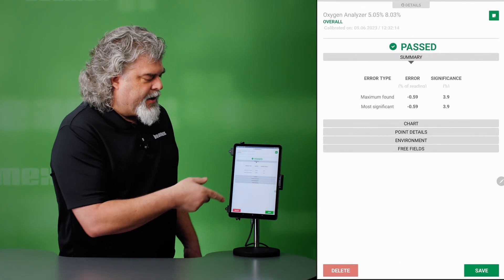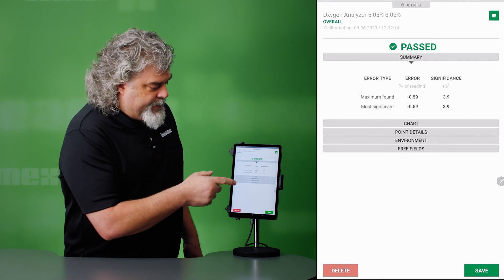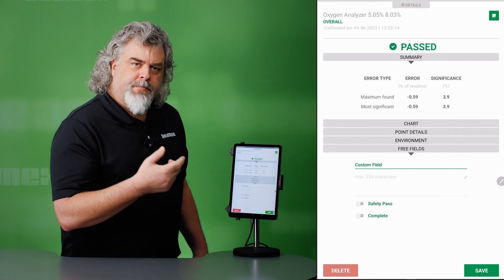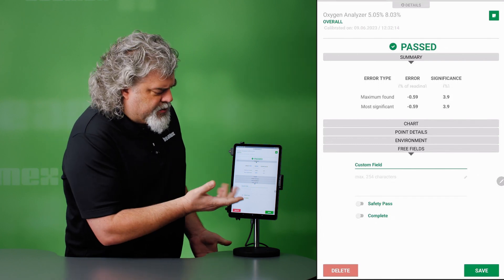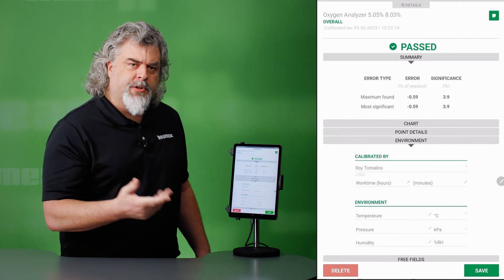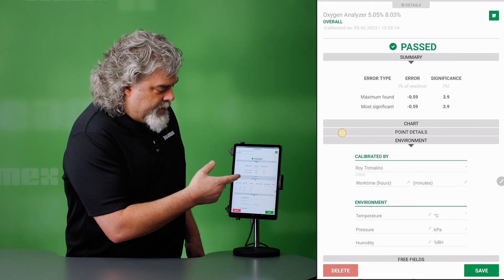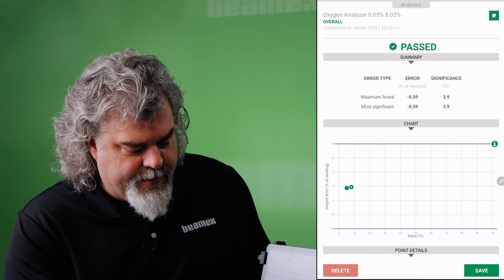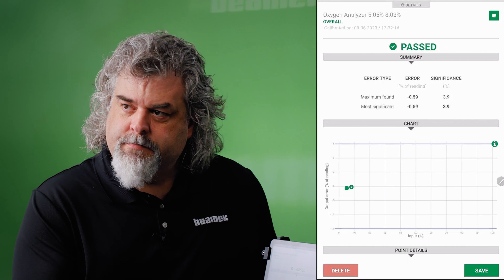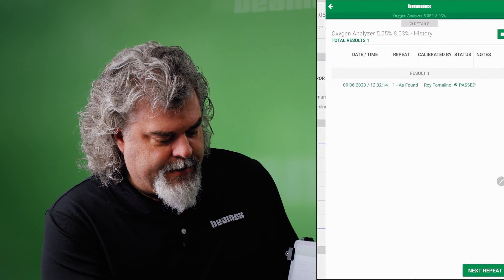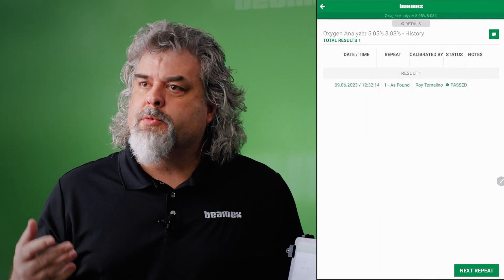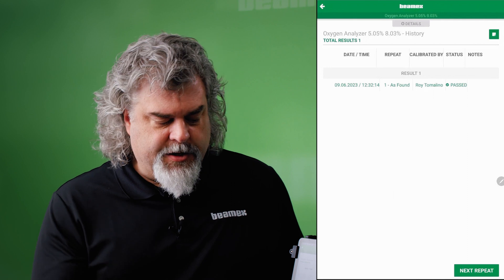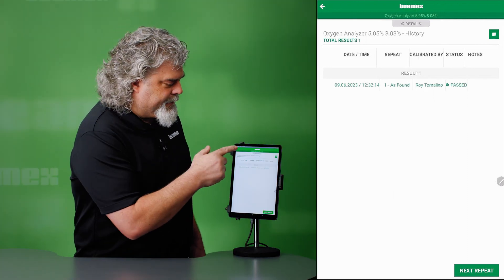Okay, this did pass as well. So same thing, we get a maximum error displayed. And let me just start in the bottom here. We have the same free fields that were predefined to start with. And you don't need to use those. Environmental conditions. What's the ambient temperature? Well, you can put that in. Here's our point numbers. And then we get the graph again. Now save it. I'll save this as found. And I'm done. Now I mentioned before doing three repeats and then getting average information. I could hit next repeat and accomplish that right here. But I'm done right here.